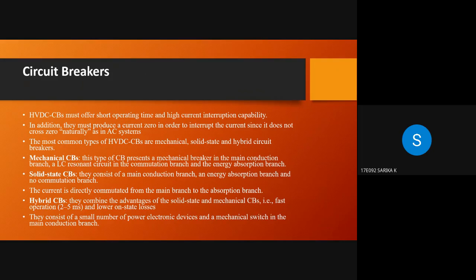First, mechanical circuit breakers. This type of circuit breaker presents a mechanical breaker in the main conduction branch, an LC resonant circuit in the commutation branch, and the energy absorption branch. Solid state circuit breakers. They consist of a main conduction branch, an energy absorption branch, and no commutation branch. The current is directly commutated from the main branch to the absorption branch.